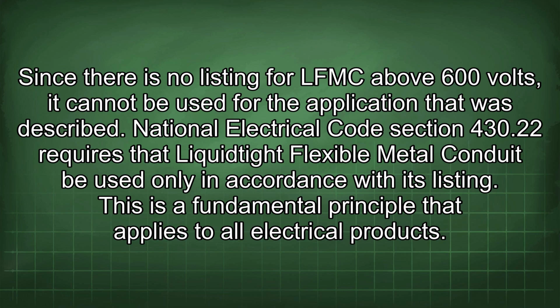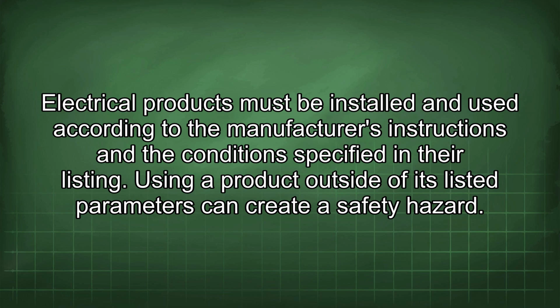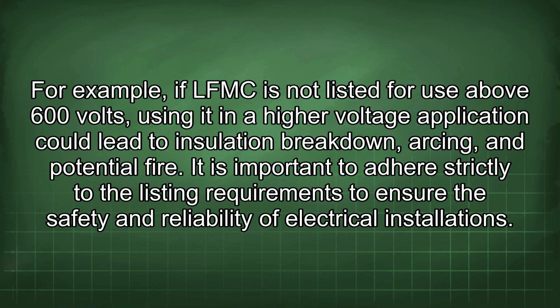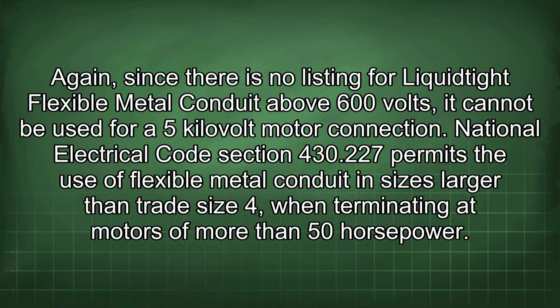National Electrical Code Section 430.22 requires that Liquidtight Flexible Metal Conduit be used only in accordance with its listing. This is a fundamental principle that applies to all electrical products. Electrical products must be installed and used according to the manufacturer's instructions and the conditions specified in their listing. Using a product outside of its listed parameters can create a safety hazard. For example, if LFMC is not listed for use above 600 volts, using it in a higher voltage application could lead to insulation breakdown, arcing, and potential fire. It is important to adhere strictly to the listing requirements to ensure the safety and reliability of electrical installations. Again, since there is no listing for Liquidtight Flexible Metal Conduit above 600 volts, it cannot be used for a 5 kV motor connection.